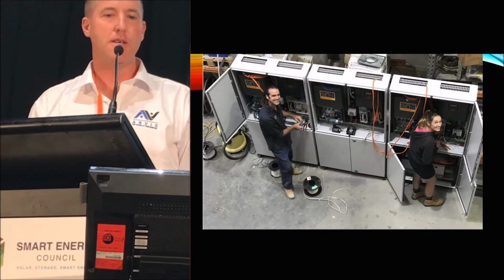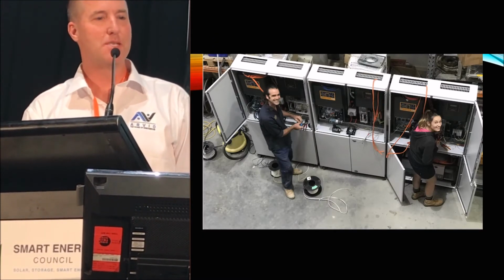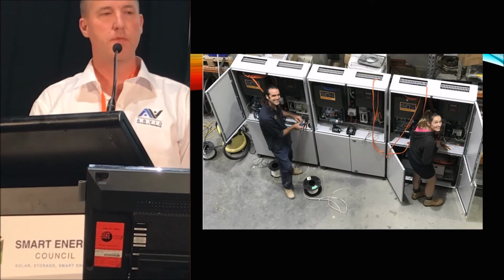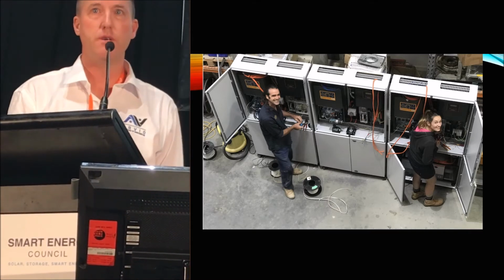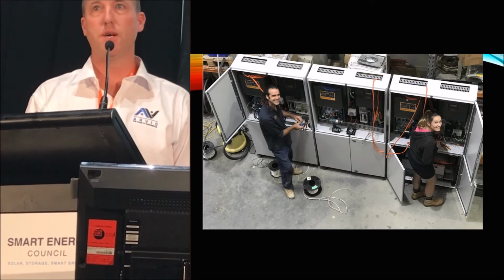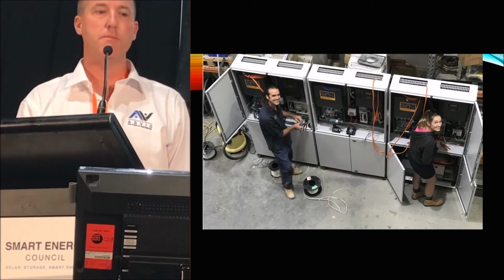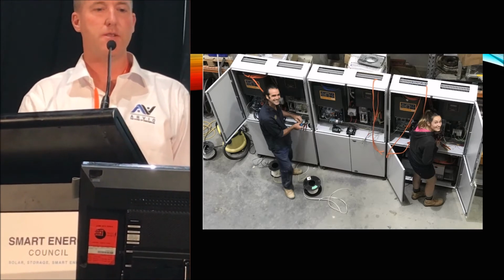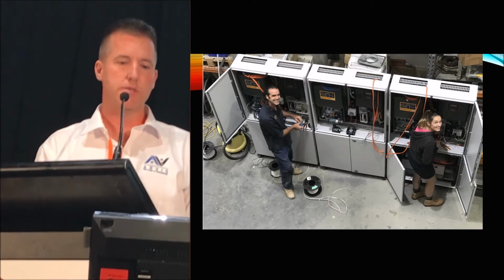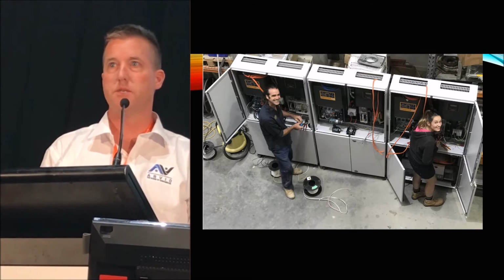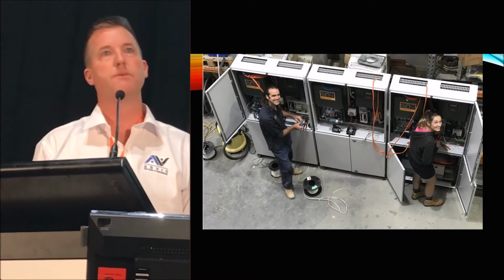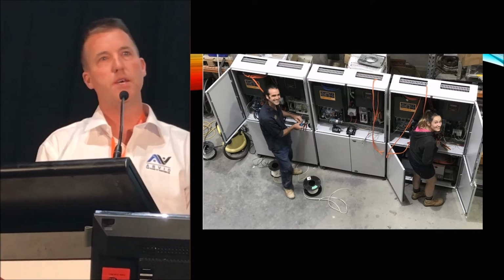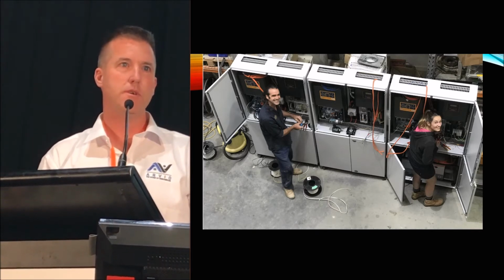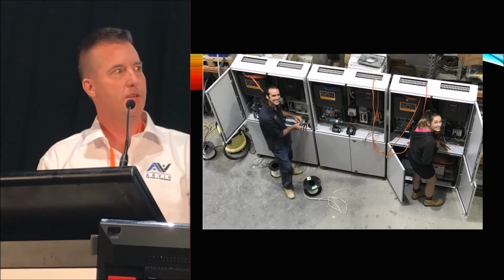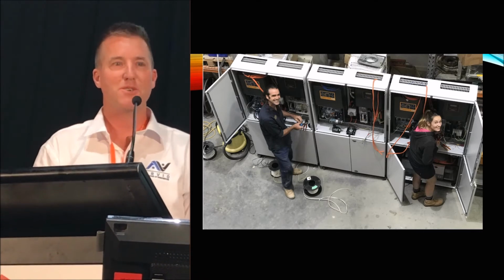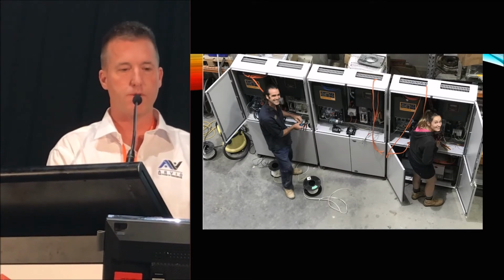This is a system that Marty and Adele put together, which is the biggest one we've done so far. It's a full 3-phase system. So the Emacs product I talked about earlier with a remote access protocol in it lets us plug into 3 SP Pros and do full remote monitoring of the system. This one's now live in Warrandyte in Melbourne, and it's got 3 7.1 kilowatt hour supercapacitor modules in parallel, giving us 21.3 kilowatt hours of total storage, and peaking power off this chart. So that'll peak at around about, the inverters are the limit basically. You can't draw enough power from them to cause any damage.